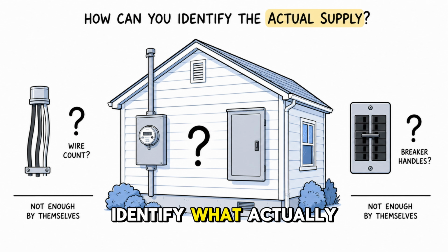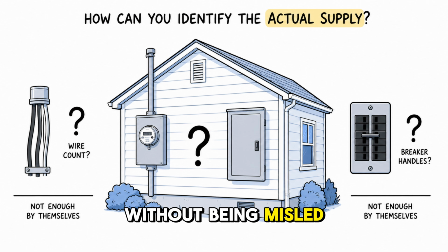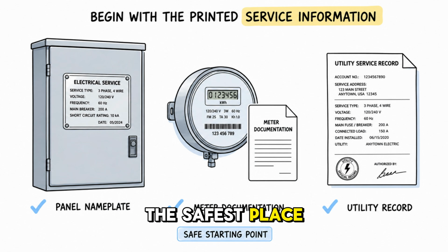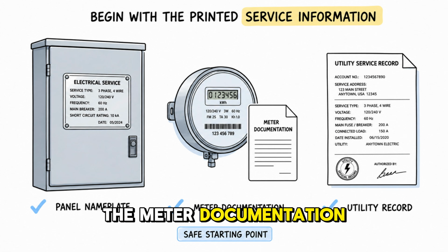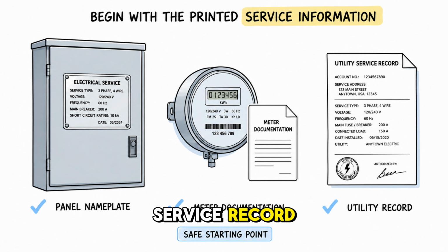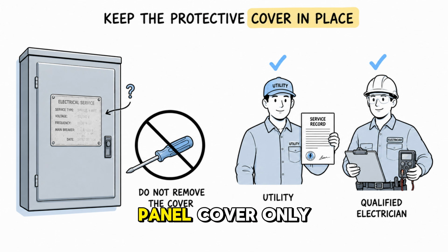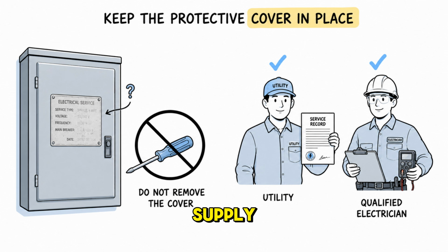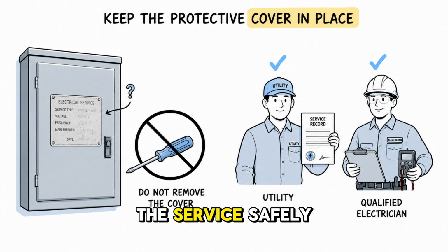How can you identify what actually feeds your home without being misled by the number of wires or breaker handles you see? The safest place to begin is the electrical information printed on the panel, the meter documentation, or the utility service record. Never remove the protective panel cover only to identify the supply. If the label is missing or unclear, the utility or a qualified electrician can confirm the service safely.